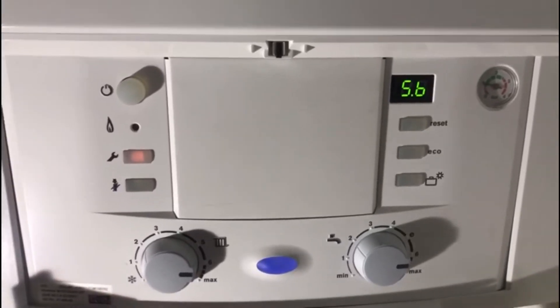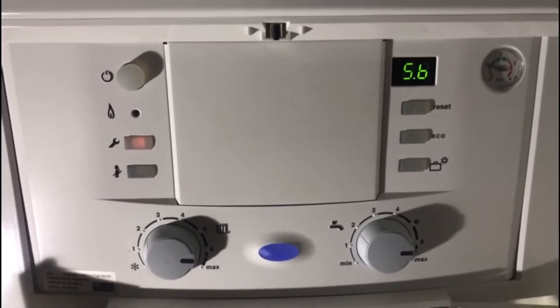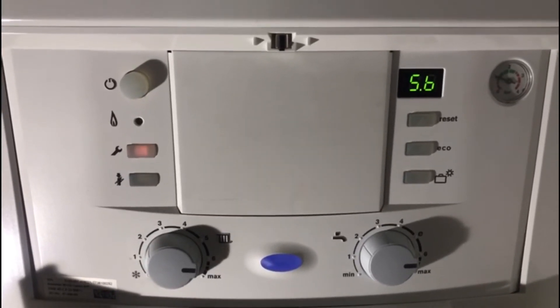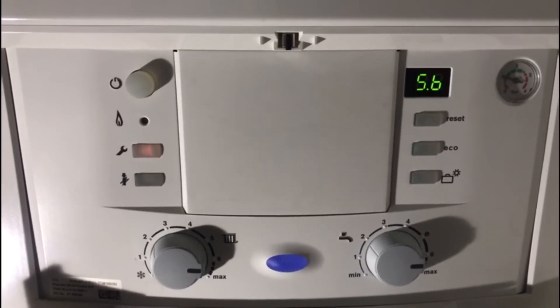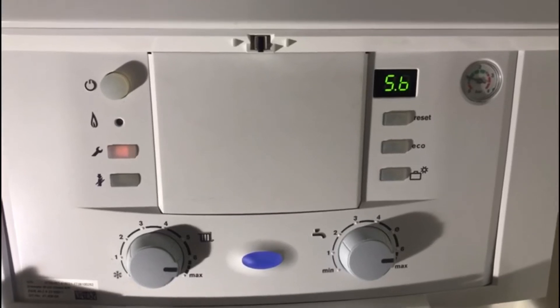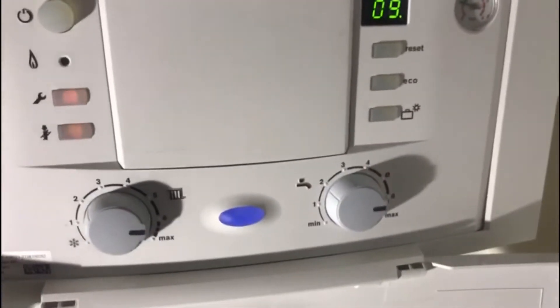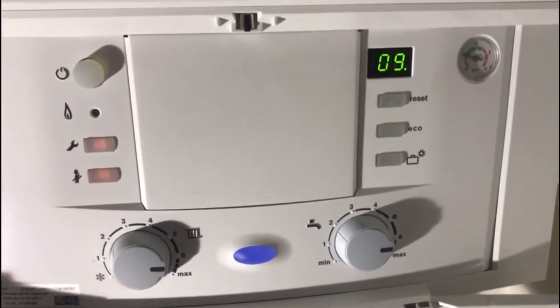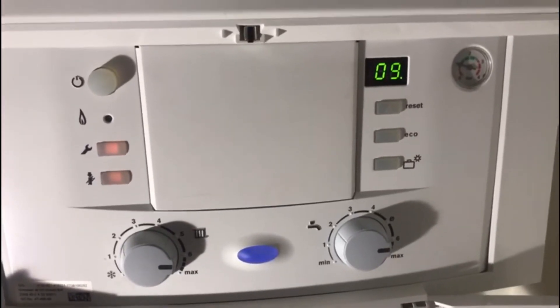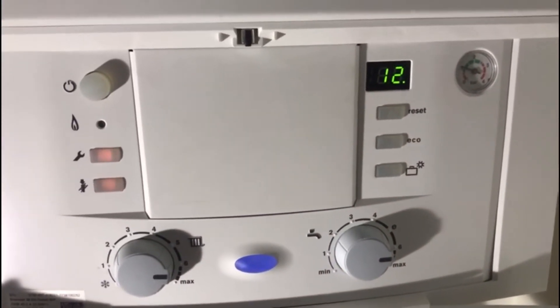Next we've got service function 5B, which is your fan overrun time. This is quite an important one. It's a fault that can show up as a lot of EA faults. EA faults can be caused by a host of different things: a blocked siphon, faulty electrodes, a gassy mixture, or a sticking burner plate. This is one solution — it essentially dries out your burner plate. It's factory set at 03, which is 30 seconds. Mine is set at 09, which is 90 seconds. The values represent seconds: 04 is 40 seconds, and so on.